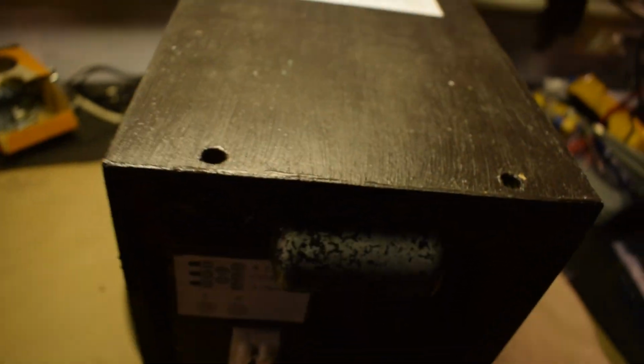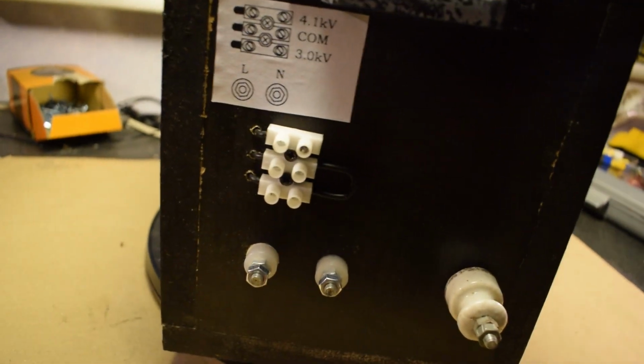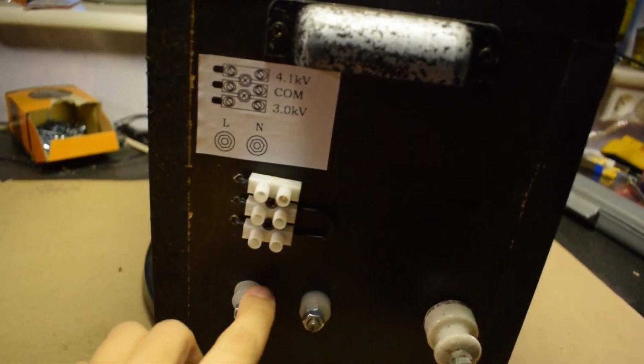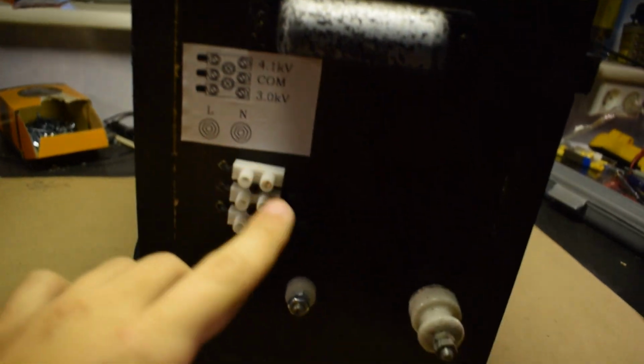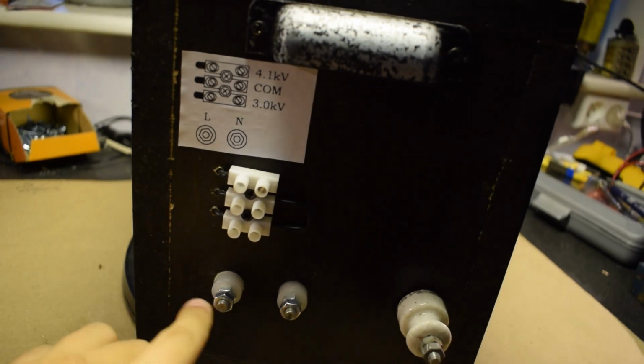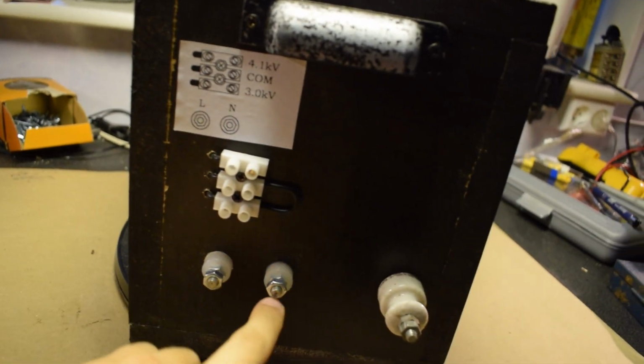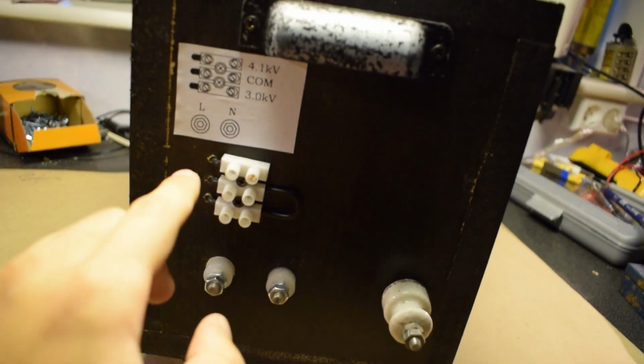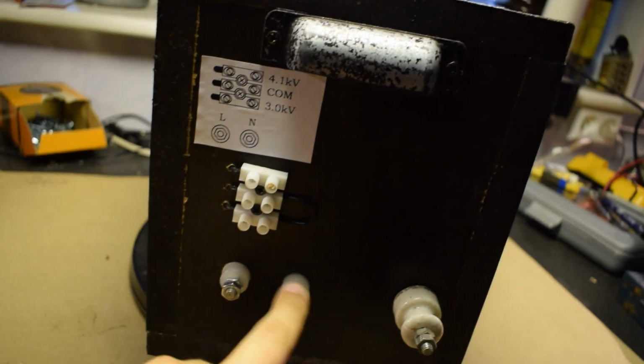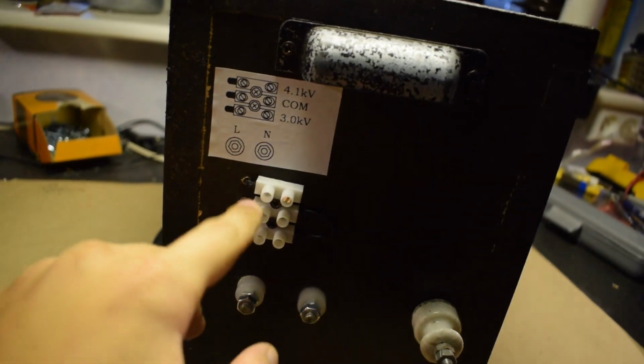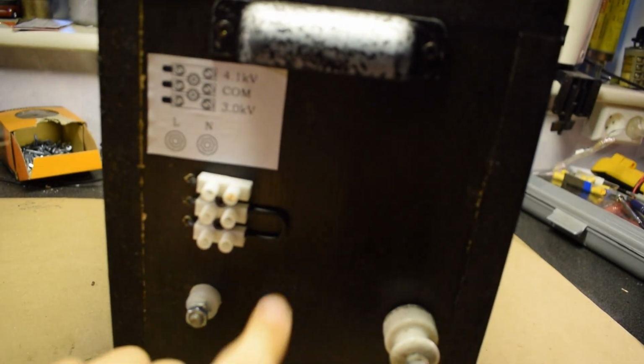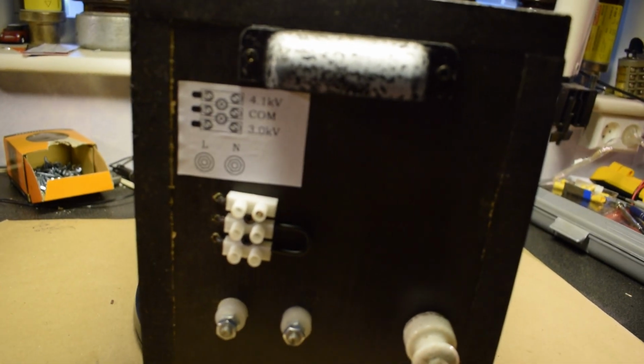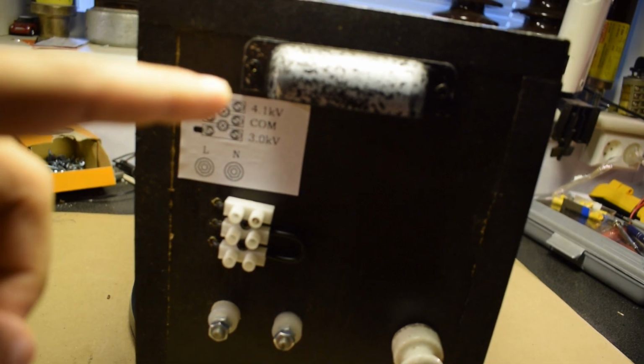If we go to the back here, you can see we have the bushings, properly labeled. These are the low voltage bushings for the input, so you have live and neutral, which should be here. Then these are the tap for switching between the ballasted and unballasted modes, and you can see the voltages you get up there.